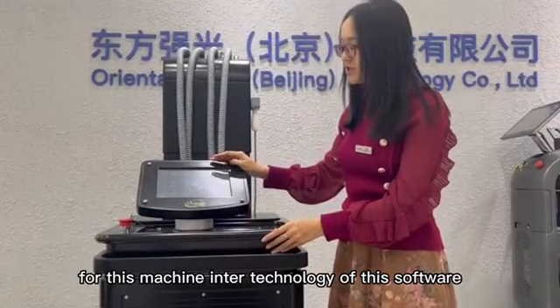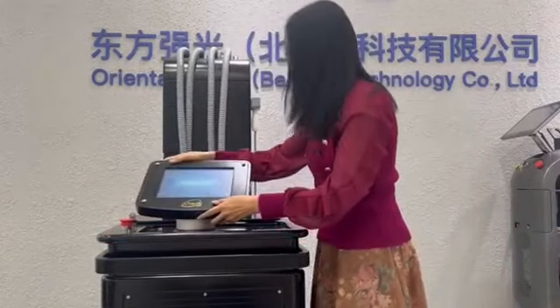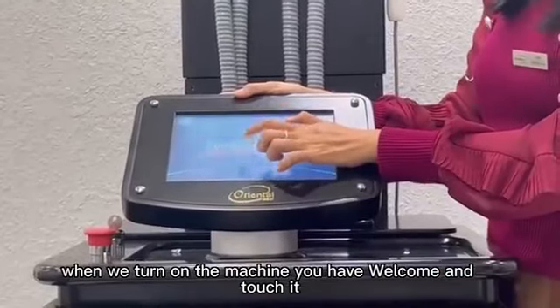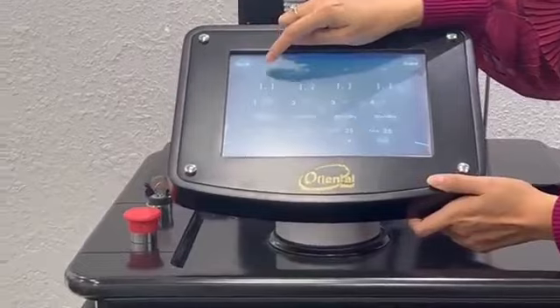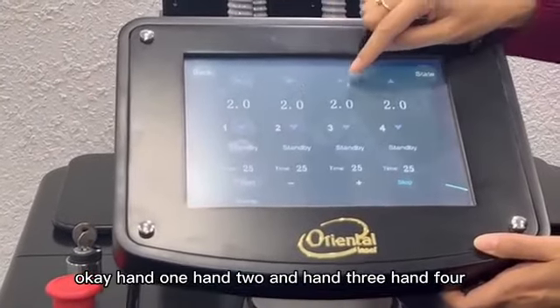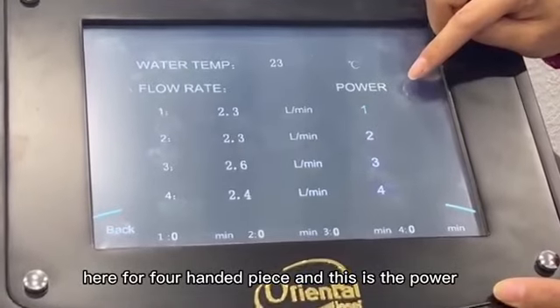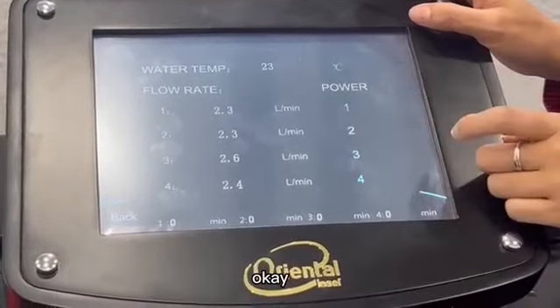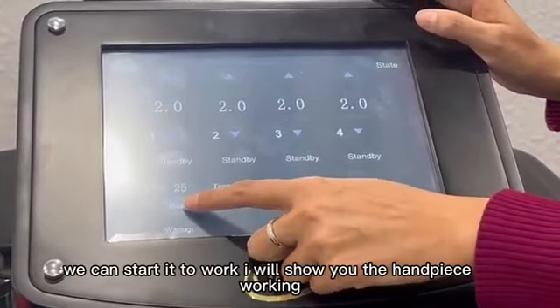For this machine, the Oriental technology software is also very easy to operate. When we turn on the machine, you will see four different handpieces, and each energy setting can be changed from 0.1 to 2.0 watts per centimeter square. We have hand one, hand two, hand three, and hand four. Here we have the flow rate for all four handpieces and the power energy grid — we can choose different grid levels for the power. On the bottom side there are different minute settings for the operation.